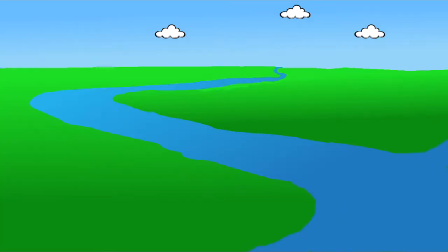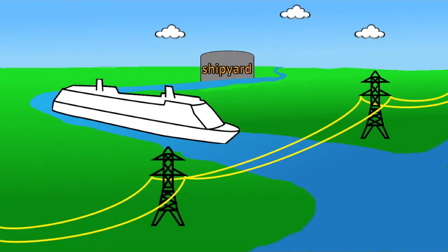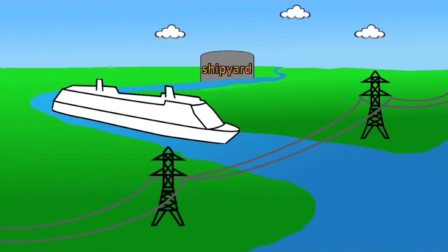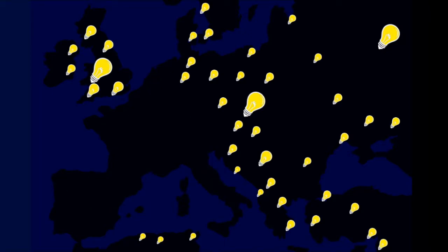In northern Germany is a shipyard which builds big cruise ships. When such a ship is completed, it is shipped via a river to the North Sea. In 2006, such a big ship was built that they had, for safety reasons, to deactivate a power line which ran across the river during the transfer of the ship. The deactivation of the line created a cascade of line shutdowns and half Europe was in the dark. This is only one example why such blackouts happen from time to time.